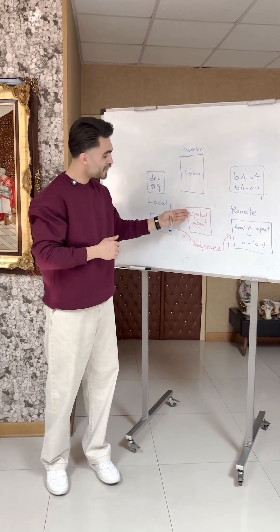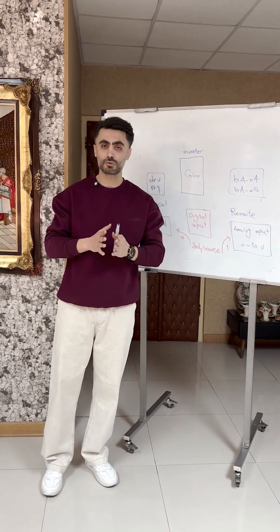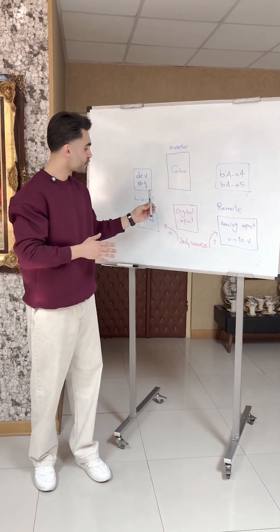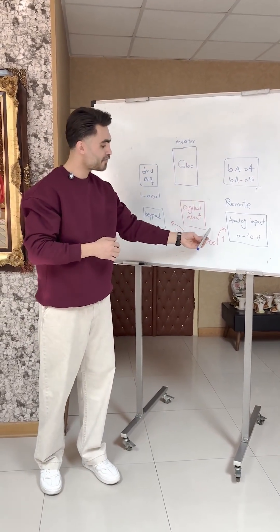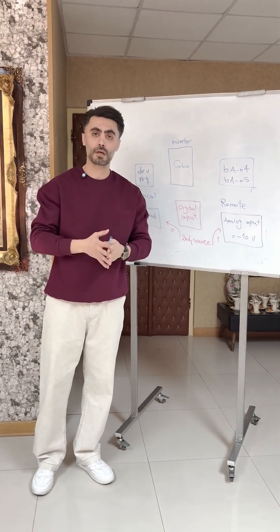But how does it work? You need to assign one of the inverter's digital inputs as you prefer to the second source mode. If this digital input is deactivated, frequency setting or start stop will be controlled from the local panel. If it is set to logic 1 or is active, both frequency setting and start or stop can be done from the remote.